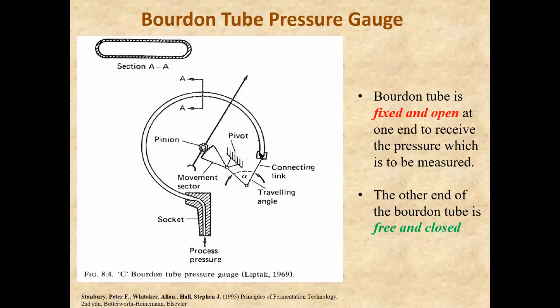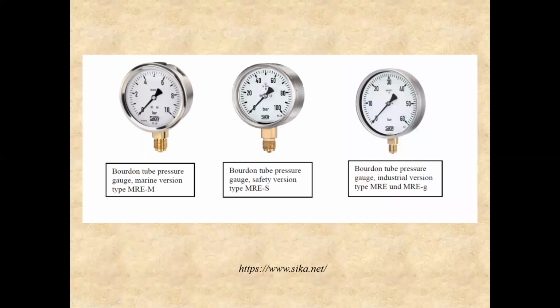And depending on how much this will move, the connecting link will move, and depending on how much the connecting link moves, the sector will move, and depending on how much the sector moves, the pinion rotates, and depending on how much the pinion rotates, the pointer moves. So this was the principle and working of the Bourdon tube pressure gauge, very commonly used in industries. And this is how a Bourdon tube pressure gauge looks from outside. These are some pictures of Bourdon tube pressure gauges.